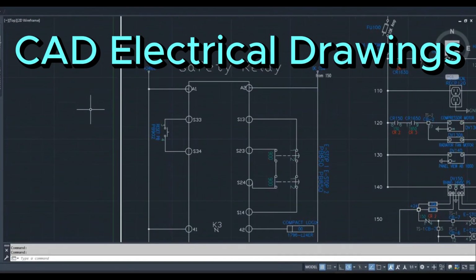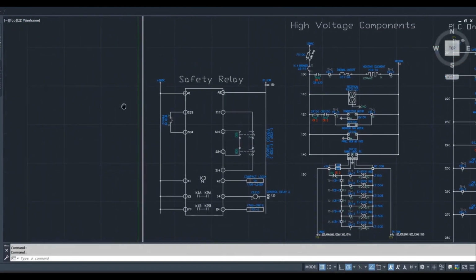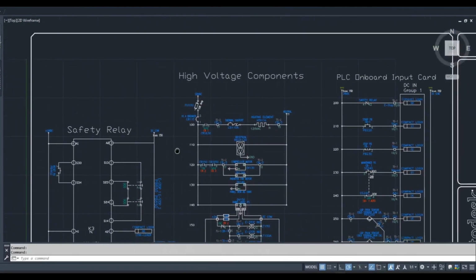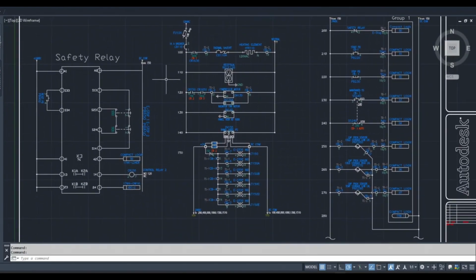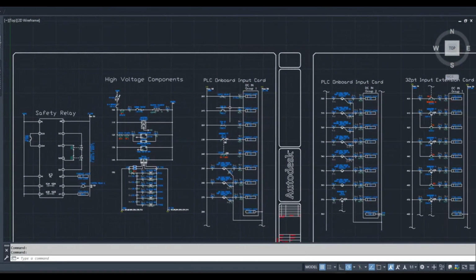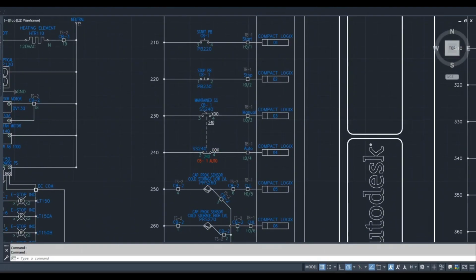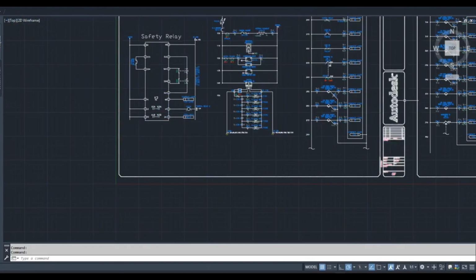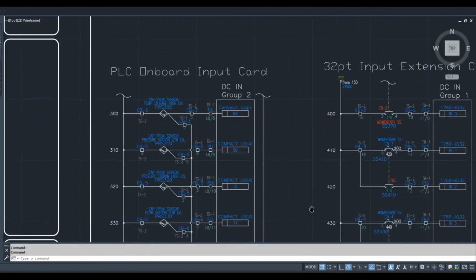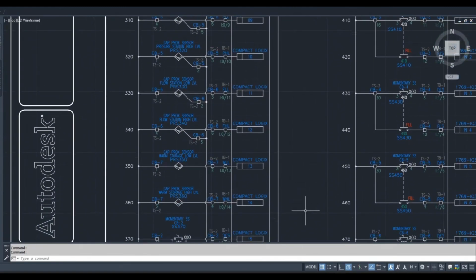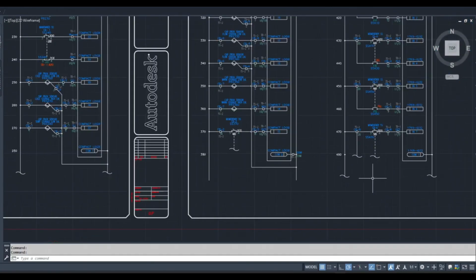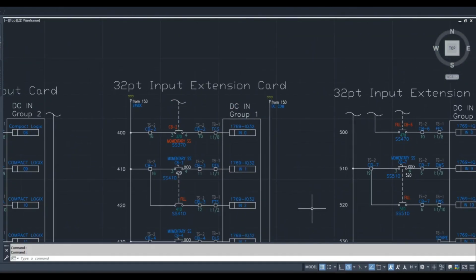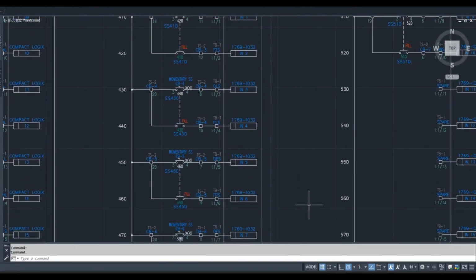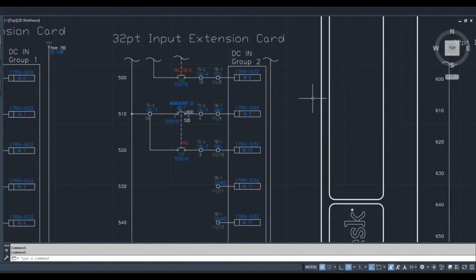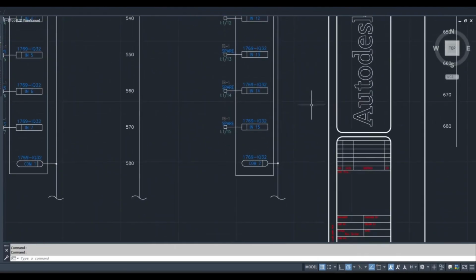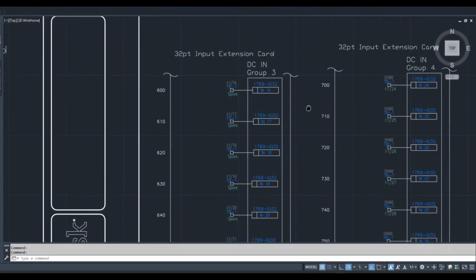Now going over the CAD electrical drawings, here's my safety relay. Then into the high voltage components like the compressor, and the heater. Emergency stop. Here's my onboard input cards for my buttons, and then going over the capacitive sensors. There's my selector switches for the manual mode. If you're draining or filling. The rest of them are just free space if you want to expand it.